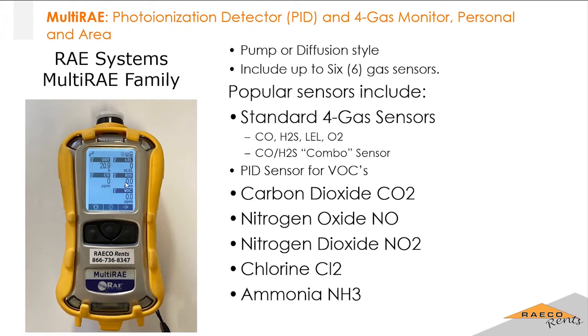Okay, so this brings us to the MultiRAE. The MultiRAE uses the same sensors as a ToxiRAE—they are interchangeable. The MultiRAE is basically like a Q-RAE and ToxiRAE all in one. It's got a PID sensor in there by default, and then it has the standard 4 gas sensors: carbon monoxide, hydrogen sulfide, LEL, and oxygen.